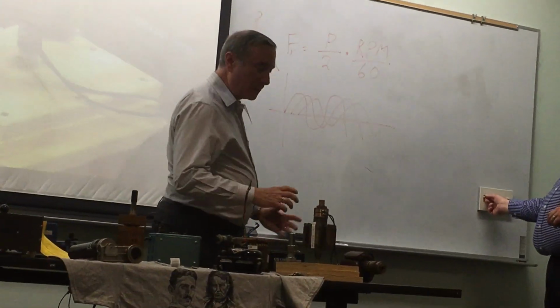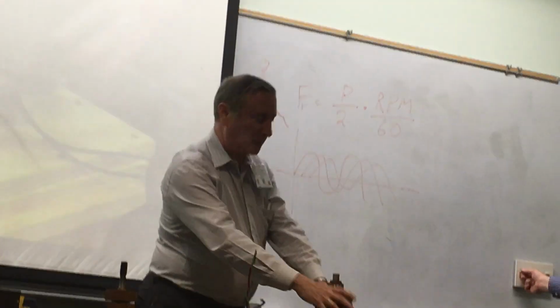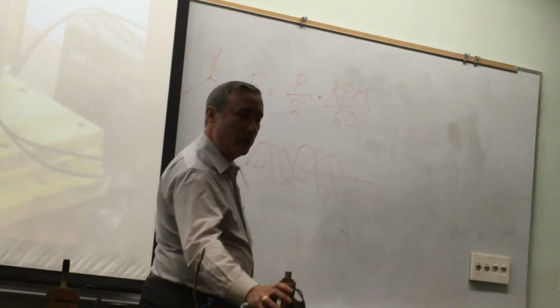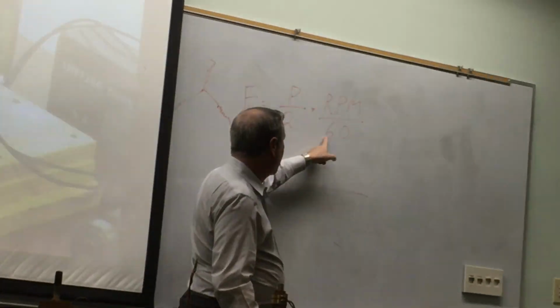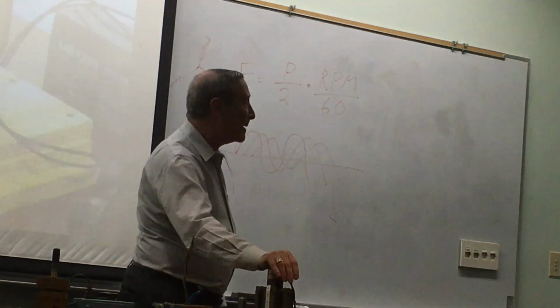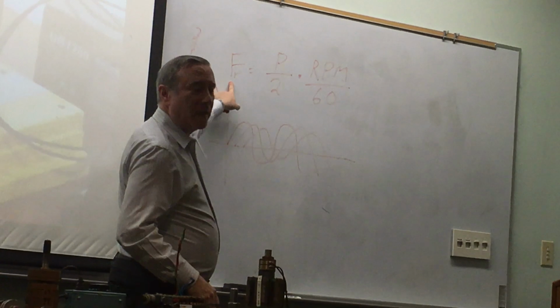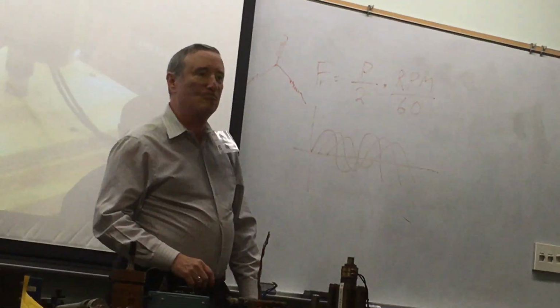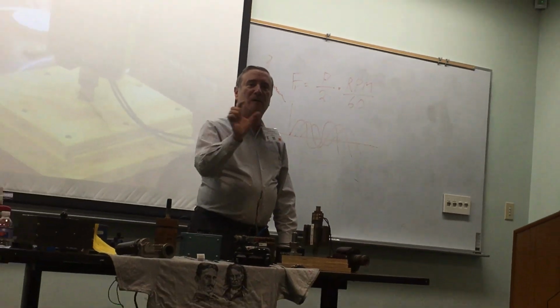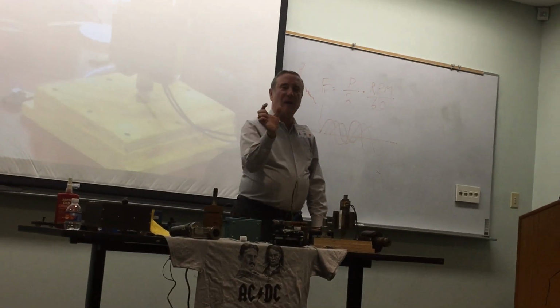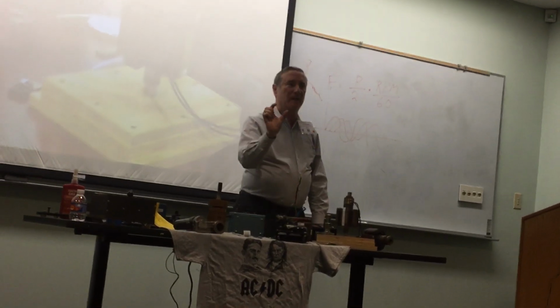Okay, to figure out the frequency of any type of generator, the frequency is equal to the number of poles divided by 2, so you've got a 6-pole rotor, times the RPM over 60. It's turning at 8,000 RPM, so the frequency of most aircraft generators is 400 cycles per second. The electrons are bouncing back and forth between the copper atoms 400 times a second.